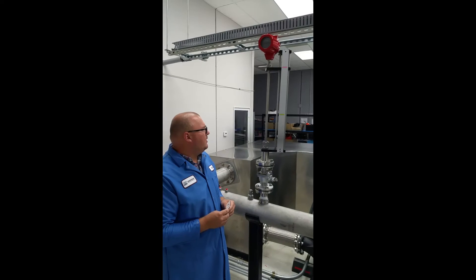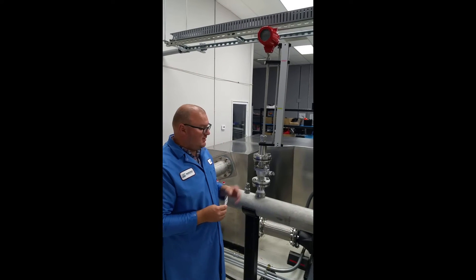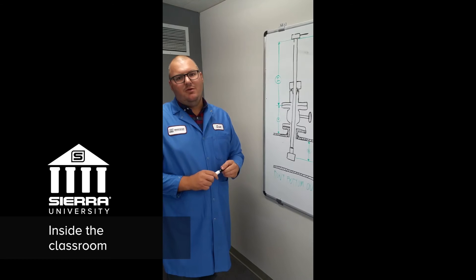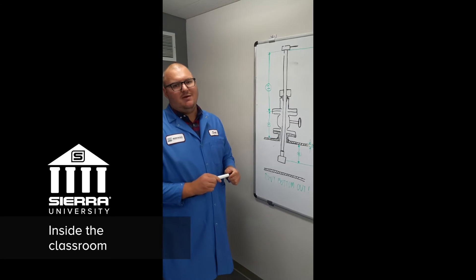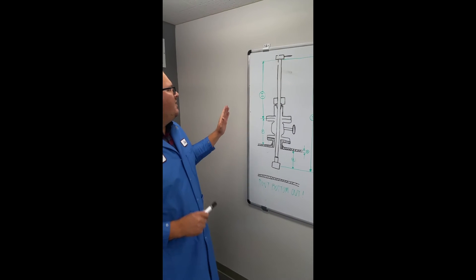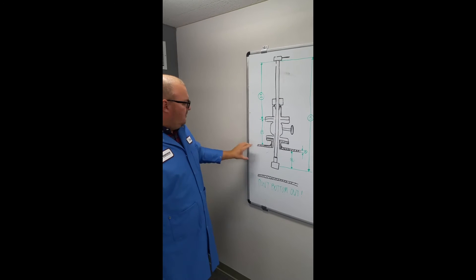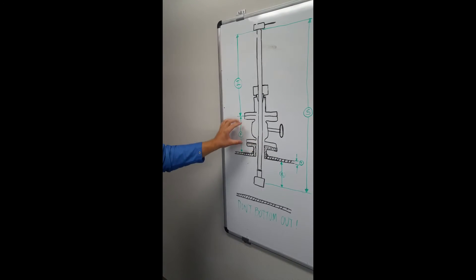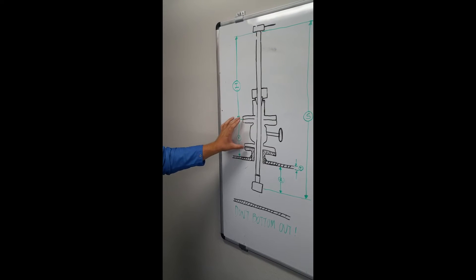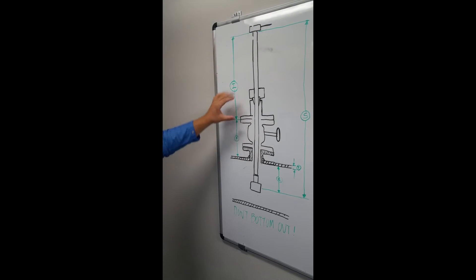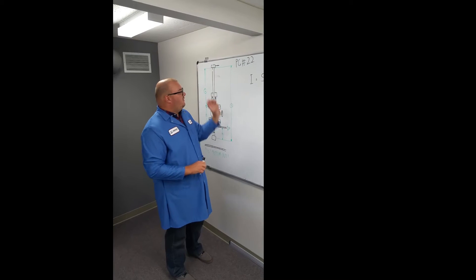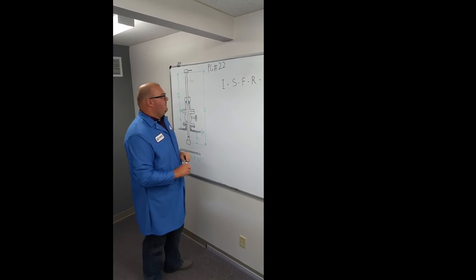How do I know how far down to insert the probe to ensure that the sensor head is in the center of my pipe? I'm here at Sierra University and I'm going to walk you through the formula we used to figure out our insertion depth. Over here I've drawn a diagram. We've got a cross section of pipe, a weldlet, a flange weldlet, and a two-inch isolation valve. This is our process connector and the probe itself. Insertion or value I is what we're trying to get.